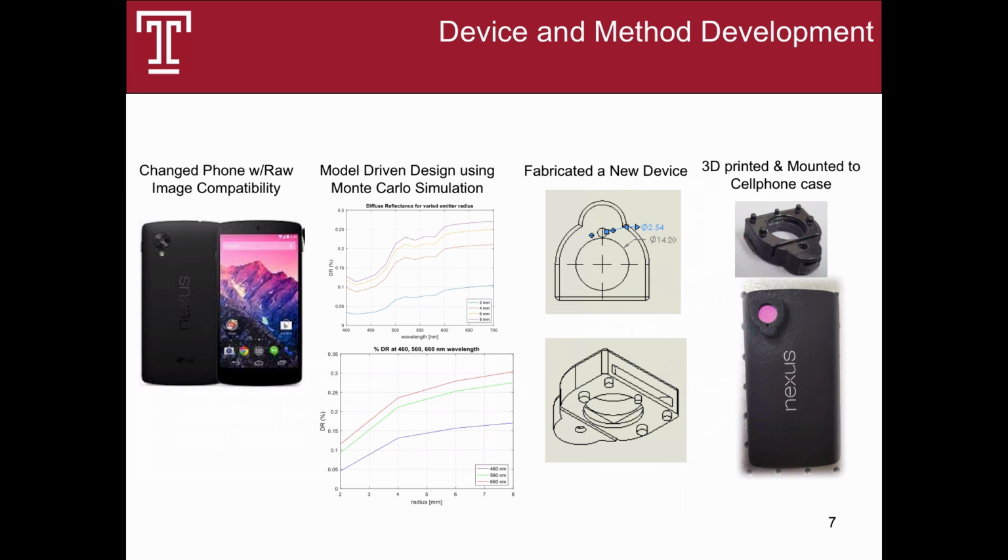What we wanted to do here is find the optimal parameters for quantifying the high amounts of bilirubin reflectance levels through our device. And what we found with our Monte Carlo model is that if we could decrease the offset between the flash and the camera, we could increase the amount of bilirubin reflectance values collected with our device. And by also tilting the flash closer to the camera, we could also increase our bilirubin concentration.